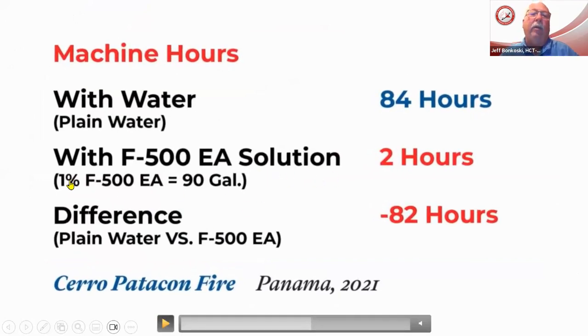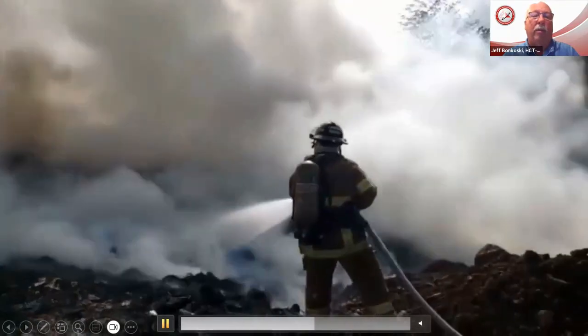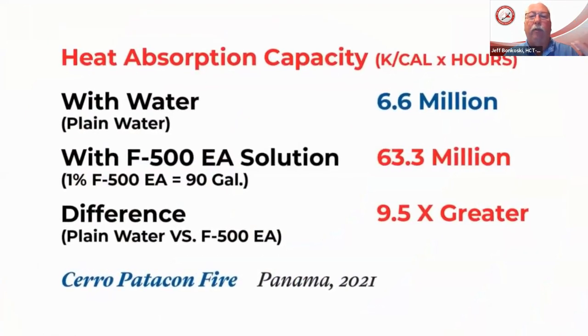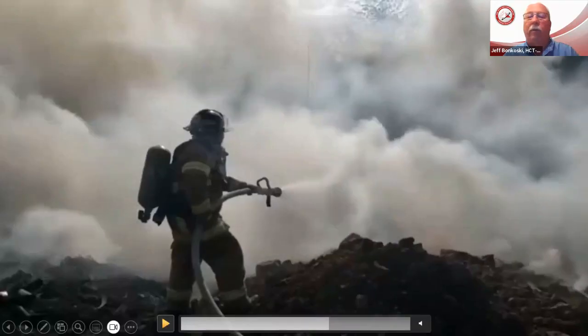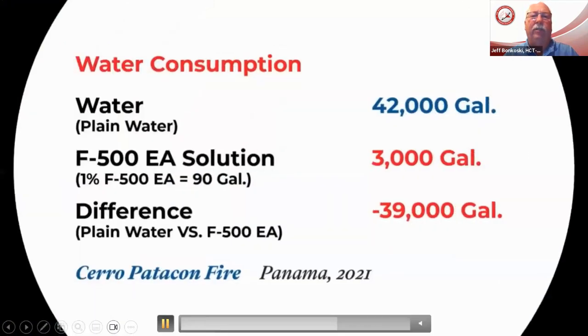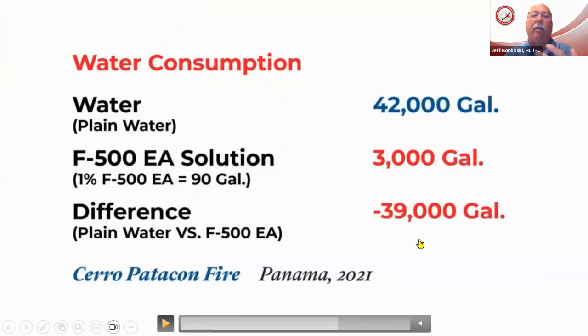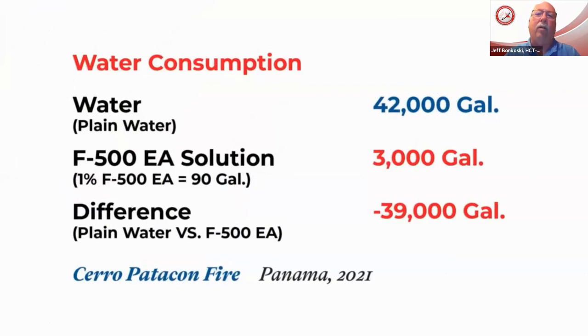Again, looking at the difference between plain water and the 1% solution of F500, the 2 hours. The thing I want to point out is while we keep showing that number of 90 gallons of concentrate, 42,000 gallons of plain water were used, but at 1%, we only used 3,000 gallons of F500 solution.